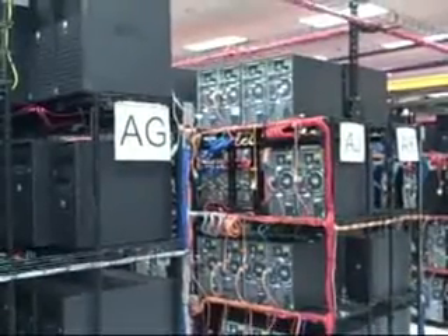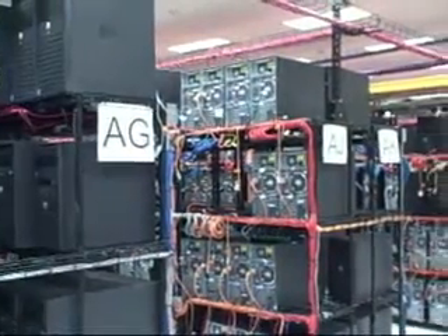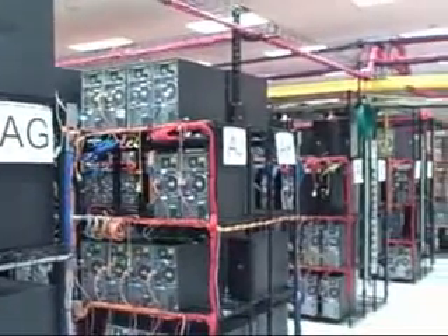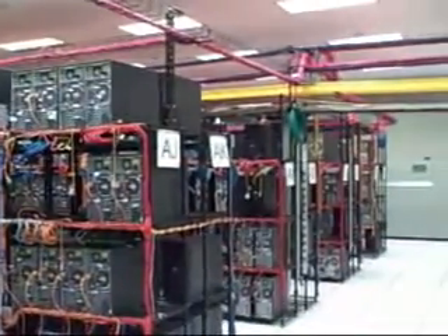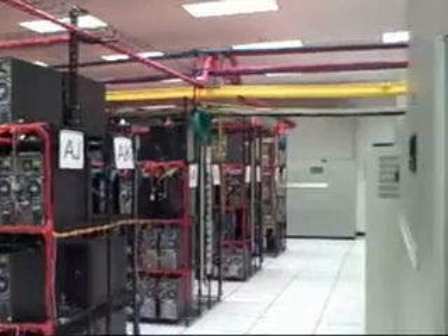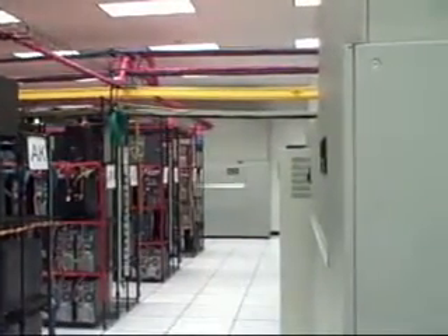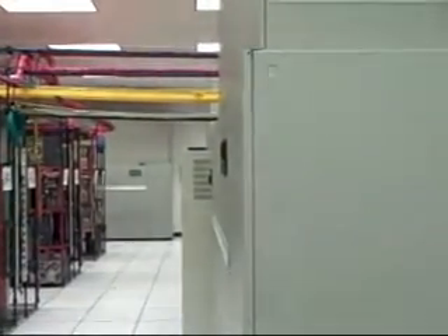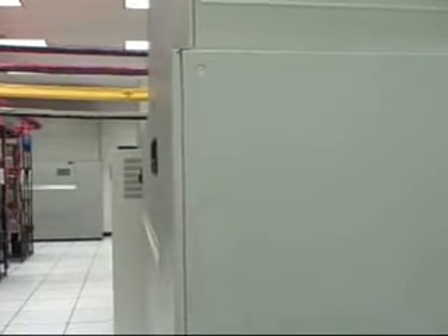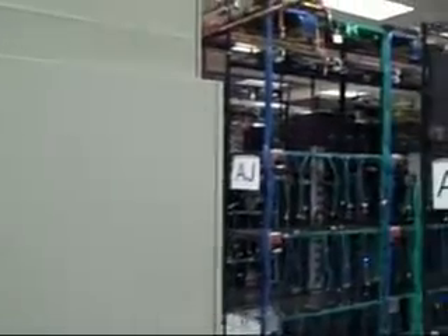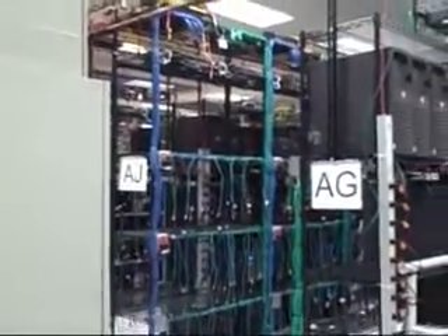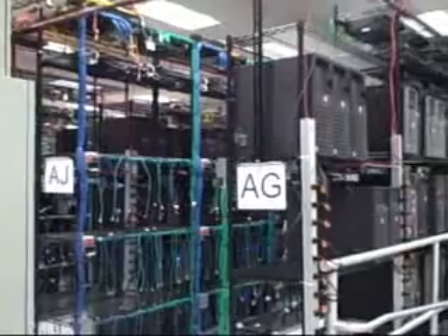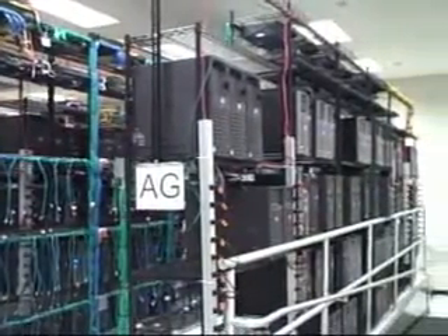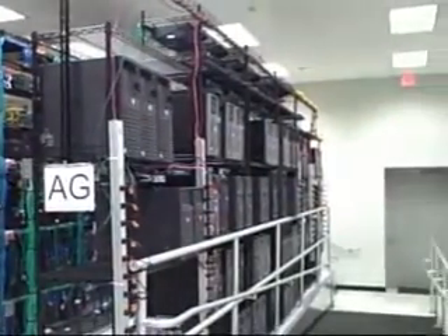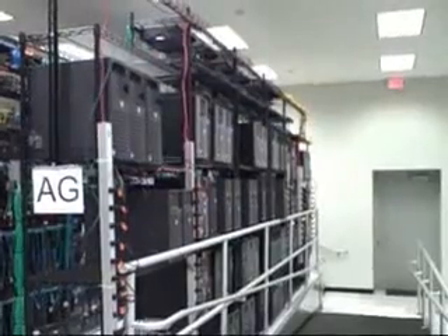This data center is just one of 6 that the Planet runs in the Houston and Dallas areas, consuming about 155,000 square feet of raised floor space. This facility was built in 3 phases. While the current phase has cabinets and rack servers, earlier phases included open racks and tower servers, as the Planet found them to be more expandable. Even with that open-air setup, good design principles can still save money.